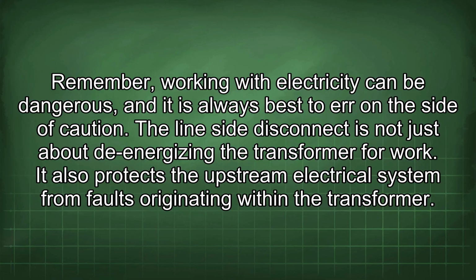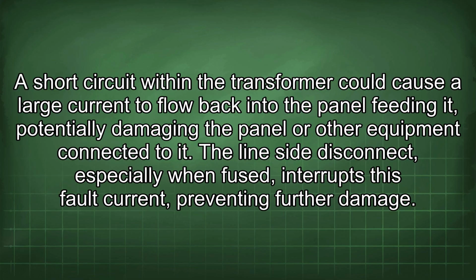The line-side disconnect is not just about de-energizing the transformer for work. It also protects the upstream electrical system from faults originating within the transformer. A short circuit within the transformer could cause a large current to flow back into the panel feeding it, potentially damaging the panel or other equipment connected to it. The line-side disconnect, especially when fused, interrupts this fault current, preventing further damage.